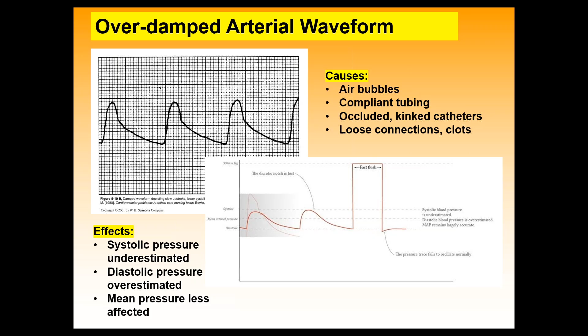Okay. So bottom line, the takeaway is to keep in mind that these indirect methods, as good as they are, they're not going to ever go away. They're just simply an estimate. So if you get complaints of why the cuff doesn't equal the direct, well, because they're different. It's up to the clinicians. The direct method, if it's done correctly, lines well preserved, maintained, is going to be the most accurate of the measurements. But this is just an estimate.